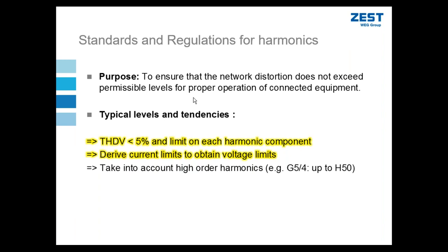Most harmonic standards tend to aim at the same thing. They want to reduce or eliminate the distortion on the voltage waveform, often in order to prevent that distorted voltage waveform from affecting other equipment or other customers, a next door plant or some other users on the system. That is generally the main criteria that the standards try to achieve. So generally, they would stipulate a limit on the total harmonic distortion of the voltage. And again, I reiterate, it becomes very important to define exactly which point of common coupling that voltage distortion limit must be applied at. And in general, that requirement is more relaxed the further downstream you get.